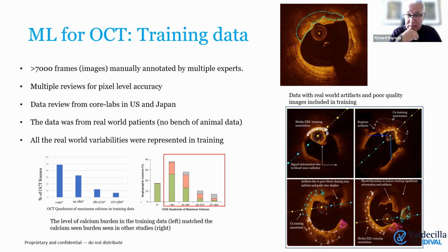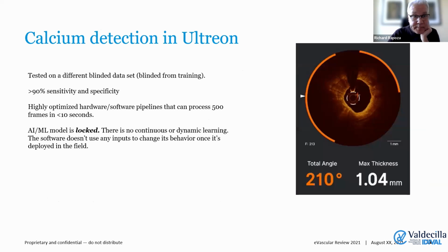And that is actually very, very important when it comes to the regulatory assessment and approval of these types of algorithms. Regulatory agencies are very wary that you may have used a very limited data set or a very homogeneous population, and that your results are not extendable to other populations. So we have to prove to them that we have the variety of patients necessary to make this applicable to as many people as possible.